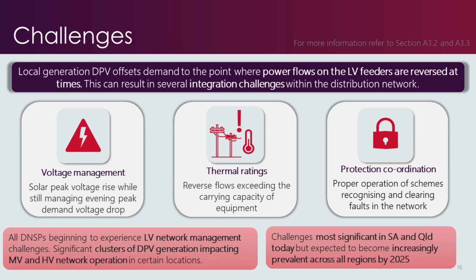What are the key challenges we're talking about? The first is managing the voltage profile. So voltage is the electrical equivalent of pressure in a water hose. DNSPs are responsible for making sure this pressure stays within an allowable range and quality of supply. DPV generation in the middle of the day, when underlying demand is low, is leading to reverse flows and voltage rise. On the flip side, networks still have to manage voltage drops that occur when flow is highest in the forward direction, that's during the evening peak. Managing this increasingly wide range of operating scenarios is probably the most significant challenge today amongst the DNSPs.